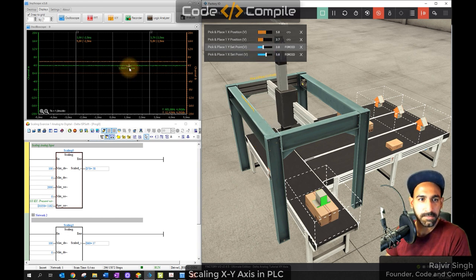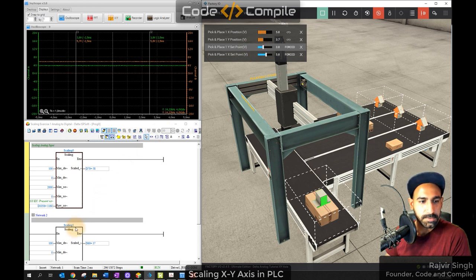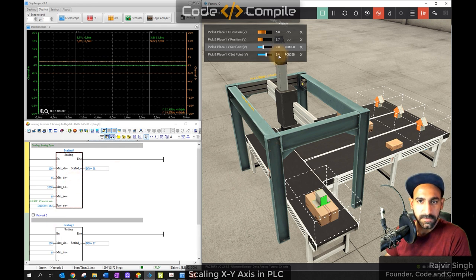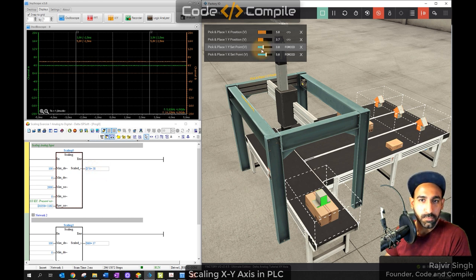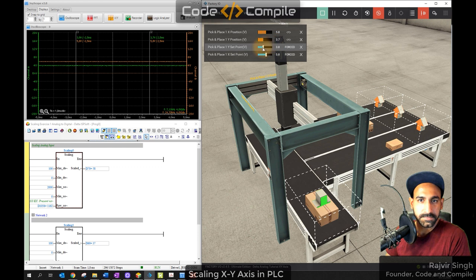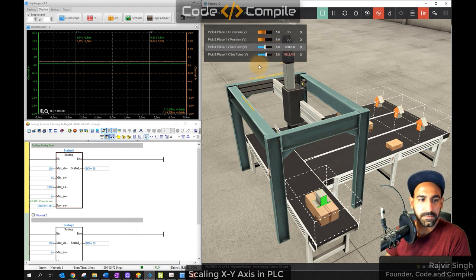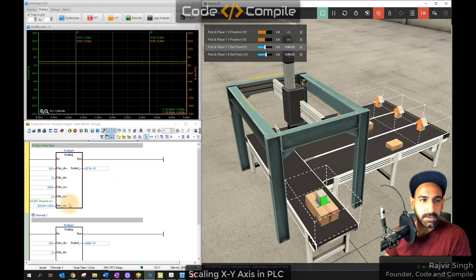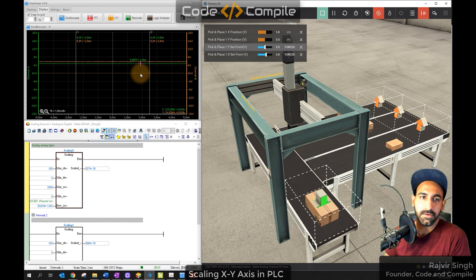So for example, this is X. So you can see that 3.3, so maximum is 10 which is the extreme location and if you see here at 10 the voltage is getting 10 volts. And if I reduce it, proportionally voltage is coming now 5.8 volts. So this is actually 0 to 10 volts feedback. Similarly, Y-axis has a feedback and Y-axis has a green curve.